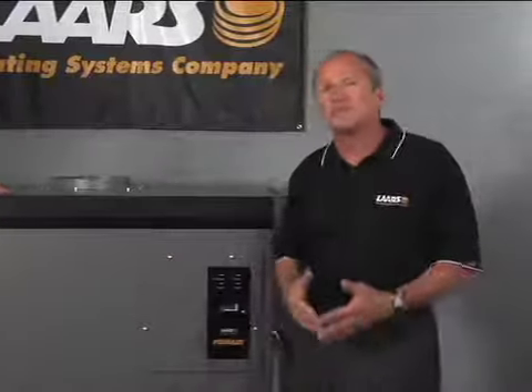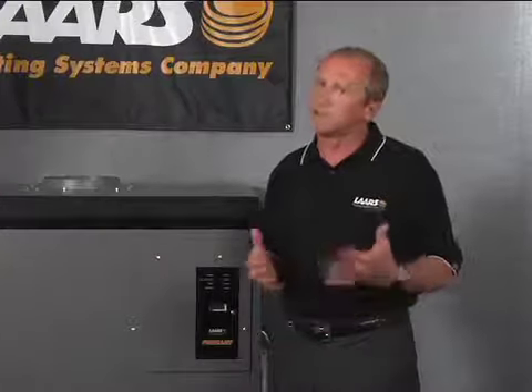and you also have the ability in most of our products to filter that combustion air, which is a really good feature. You should filter that combustion air, because in a new construction atmosphere, you have a lot of dust, you have a lot of particles in the air, and when you're sucking that stuff in, you should have the ability to at least filter it and then clean the filter.